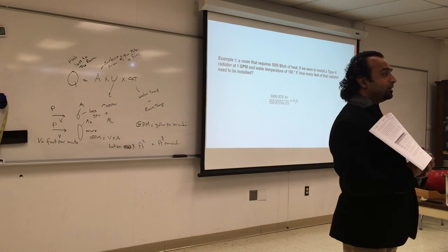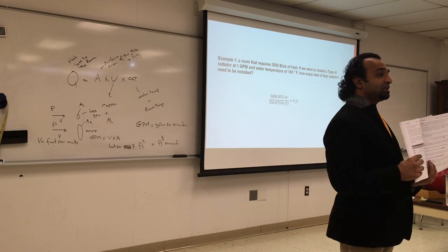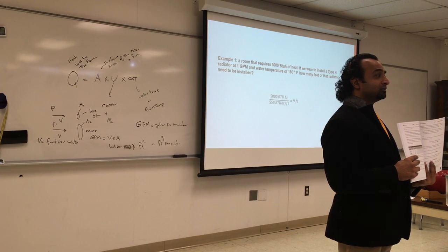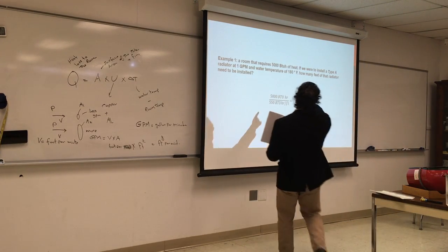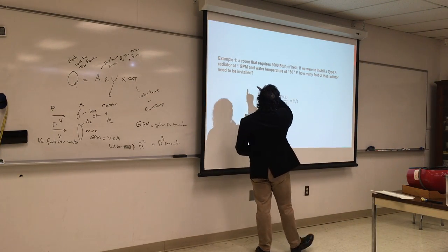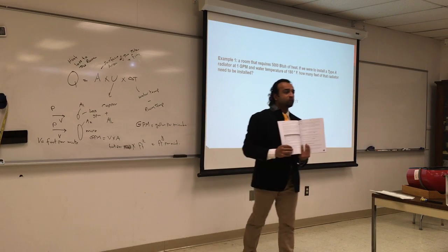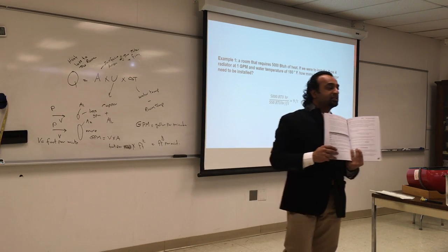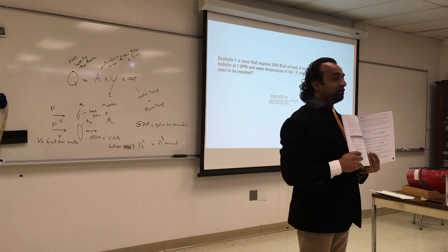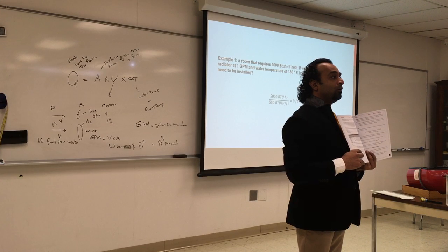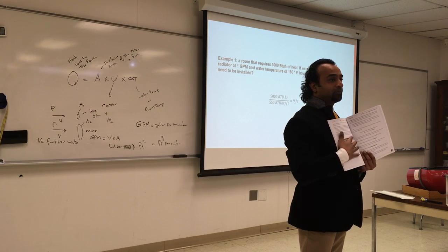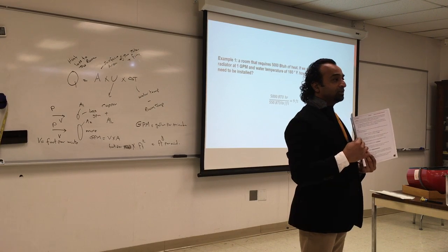Go and look up. Table lookups are the best things ever, but you just have to know what you are looking at. So look at the table. Find this criteria: 5,000, type A, water temperature, 1 GPM, and try to match that. It's important to find those three criteria because they make a difference. If the flow rate is less than 1 GPM or more than 4 GPM, it's going to be an issue. But try to stay within these numbers. This is how it was calculated.